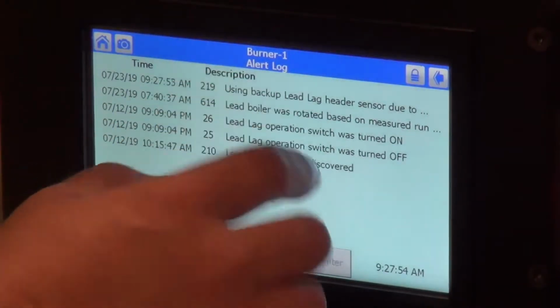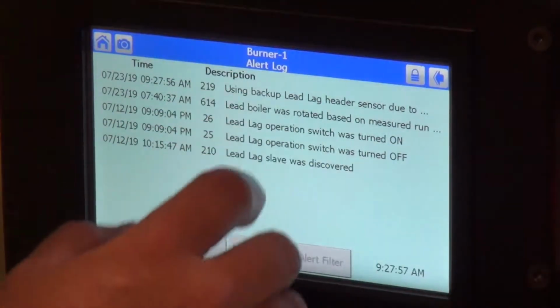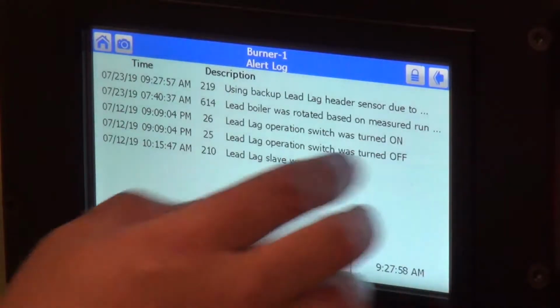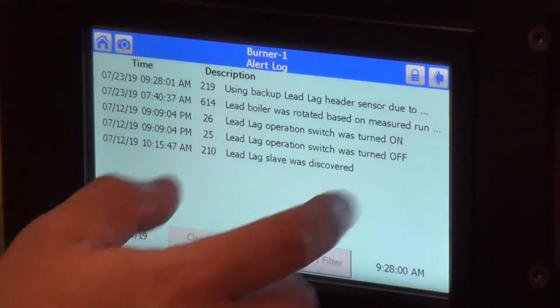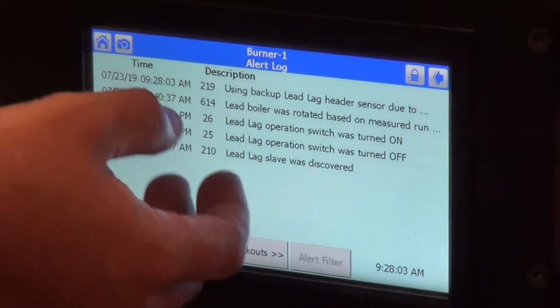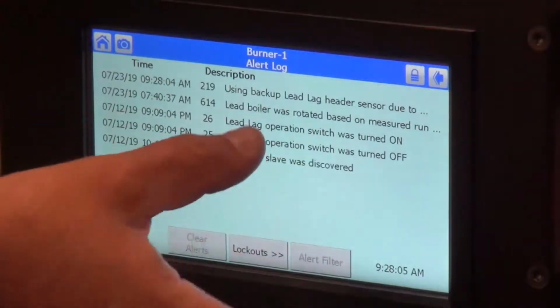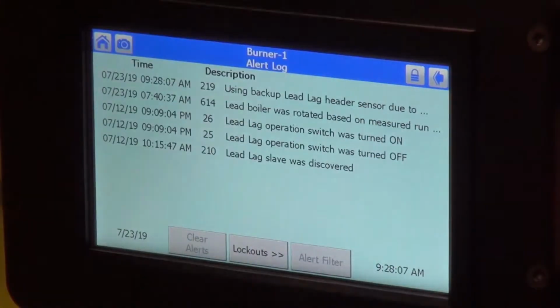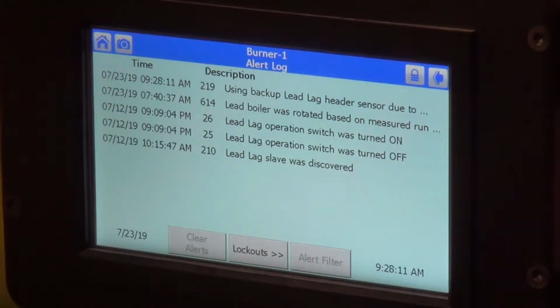Now, a lot of it is using backup lead lag header sensor, lead boiler was rotated based on a measured run, lead lag operation switch was turned on. So what this is saying is that the boiler itself is not controlling the actual rotation of the boiler operation. It's being controlled by that external controller.